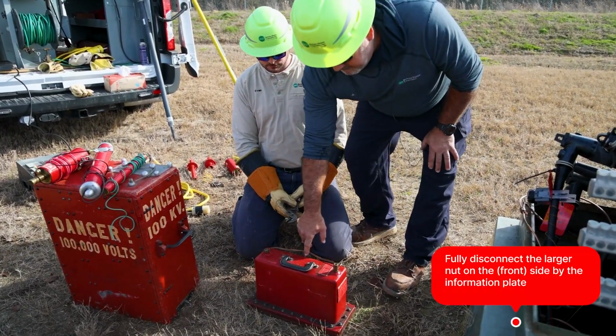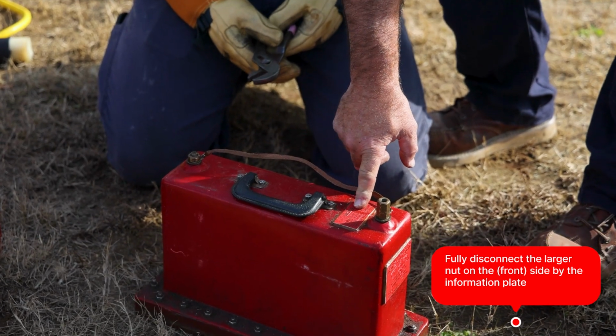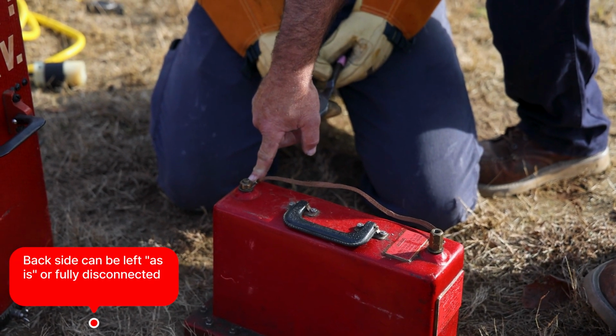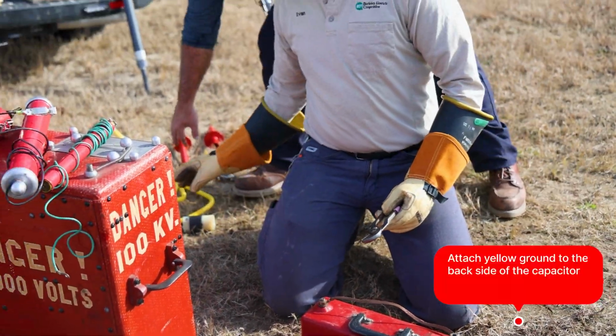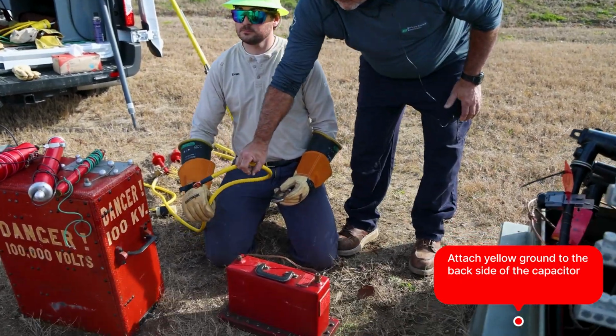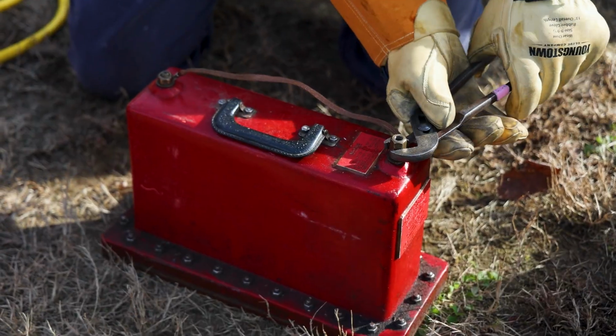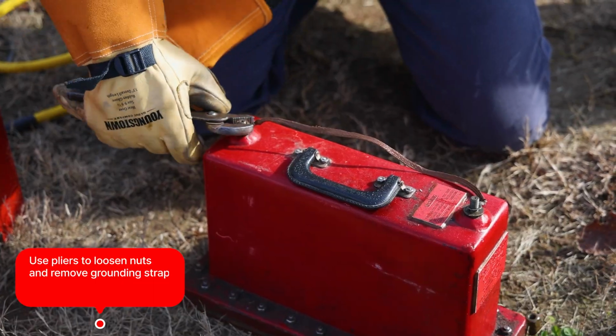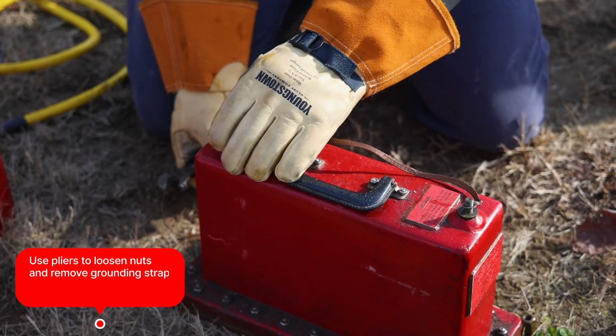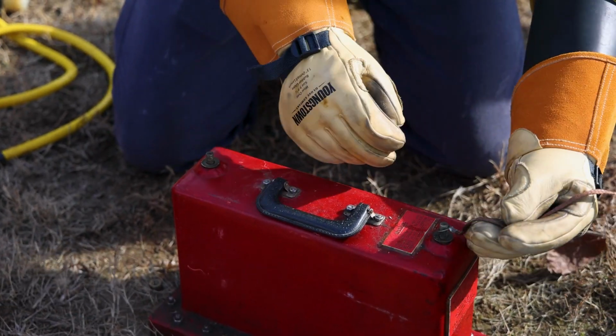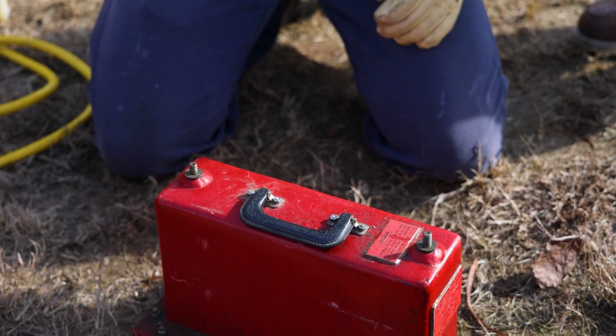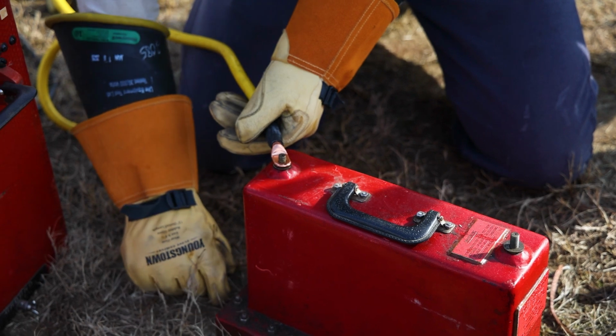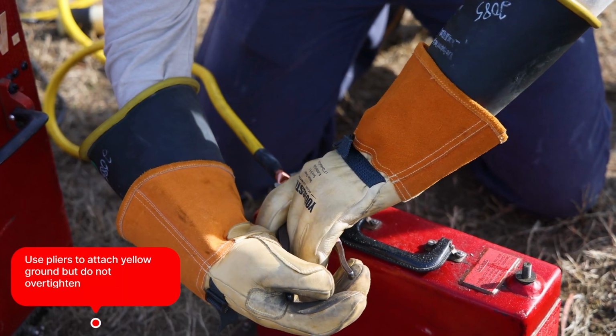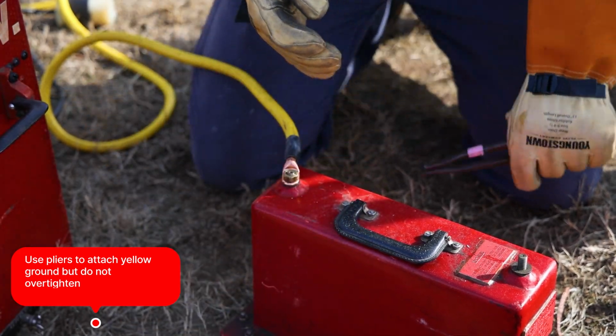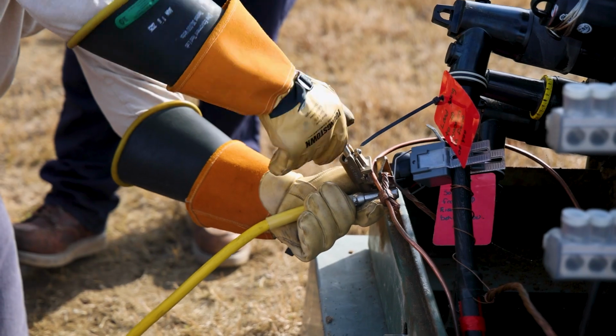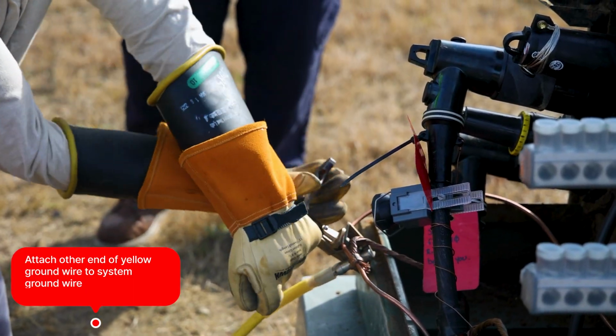When you're removing the ground strap, you need to completely take it off this side. You can leave it on this side or you can take it off completely. You attach one of your yellow grounds right here to this side of the capacitor. Once you get one side of the capacitor grounded, you need to attach your ground to your system ground.